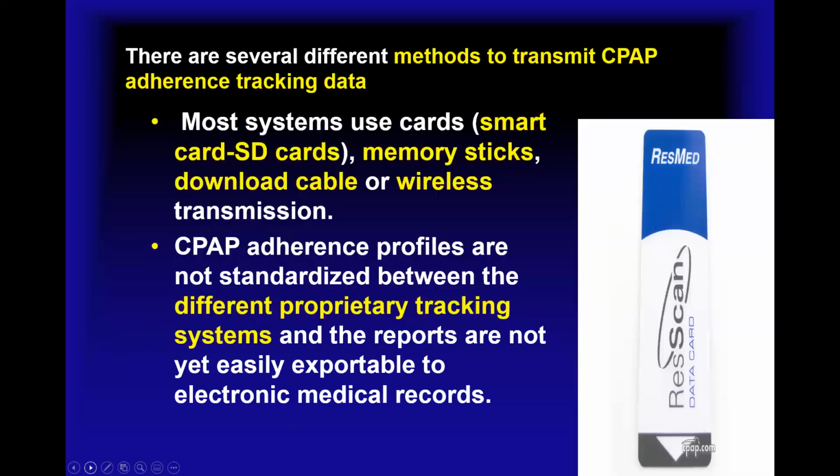Several different methods to transmit the CPAP or BiPAP adherence. Most systems use cards, smart cards, SD cards. It's similar, believe it or not, to what you have in your phone. A lot of it's wireless. It's not entirely wireless, by the way, but the mainstream is either cable or wireless transmission. CPAP adherence profiles are not standardized between different proprietary tracking systems, but there are significant similarities.